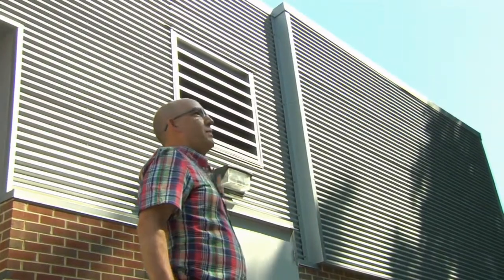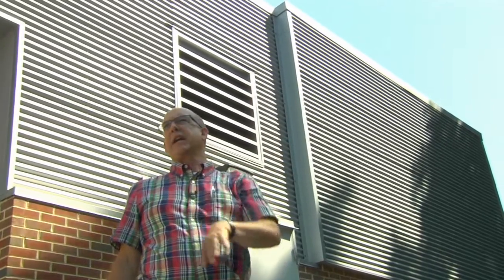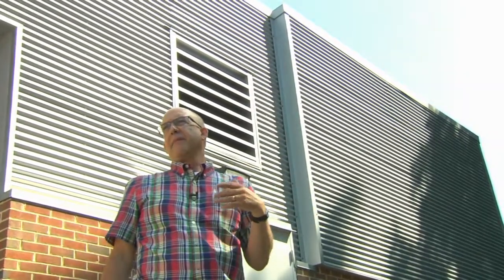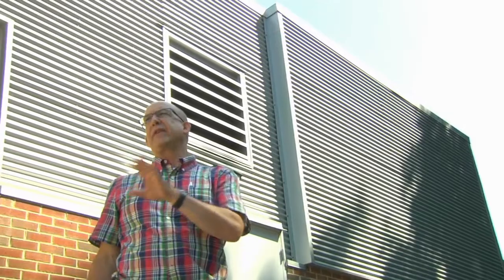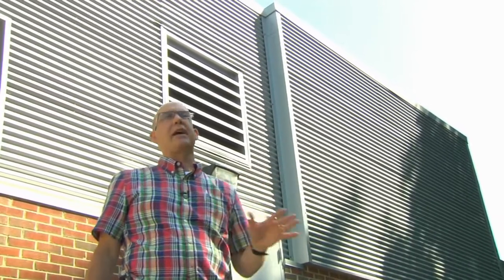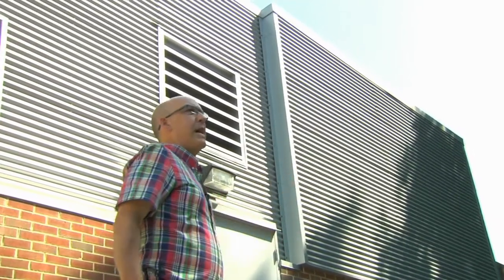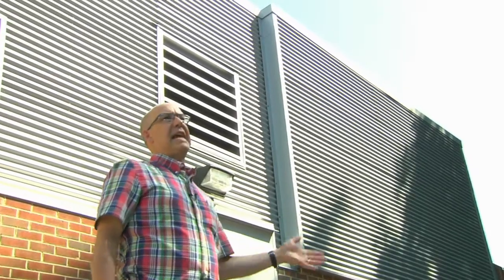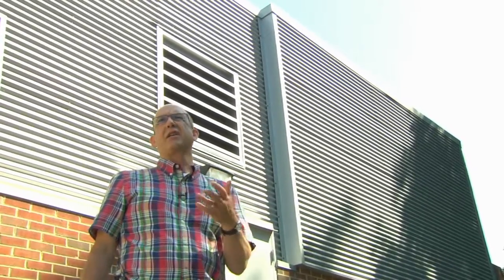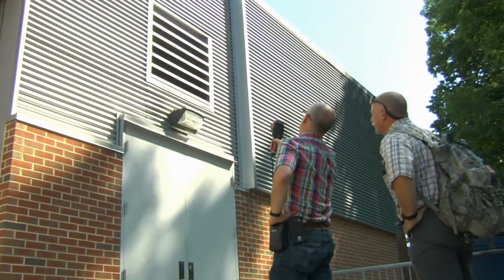This is an electrical room. I believe there's a makeup fan that's bringing air in from outside. It's on the graphic. It shows the supply fan bringing outside air in and exhausting. So you're basically moving air. It's set to maintain 85 degrees, and I saw that on the BAS as well. It's a lot of airflow.